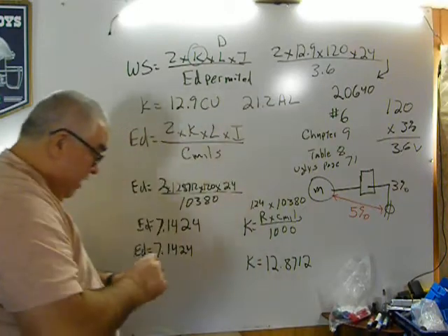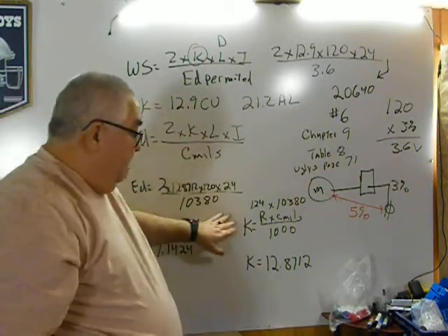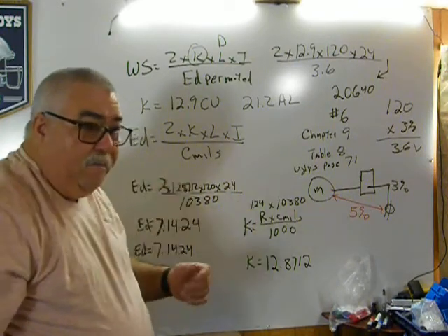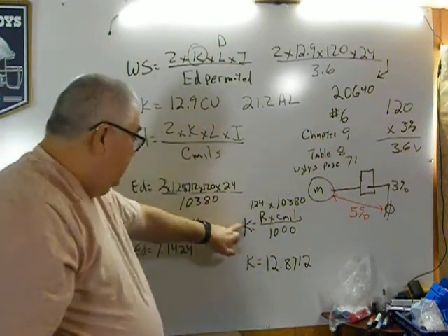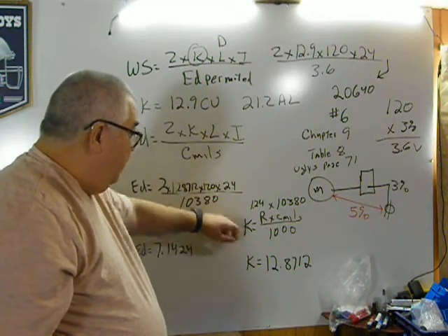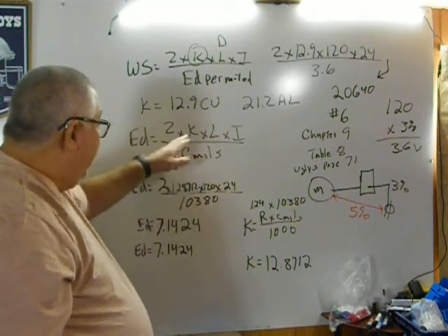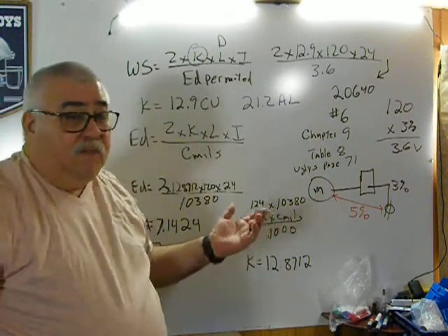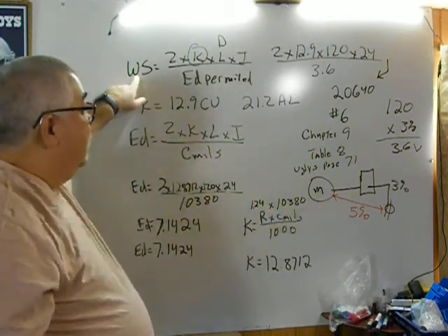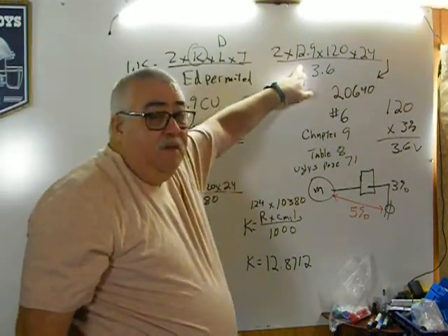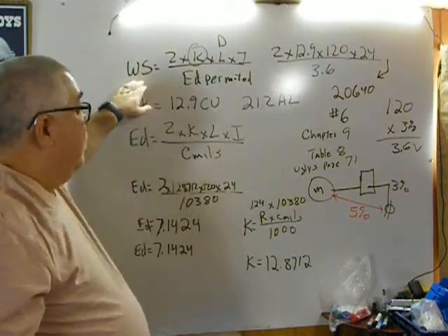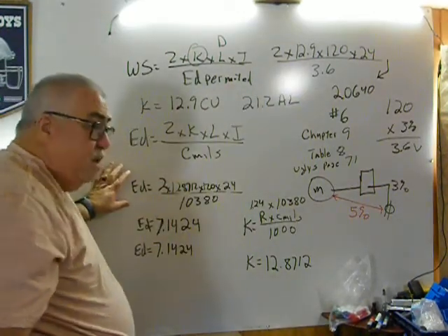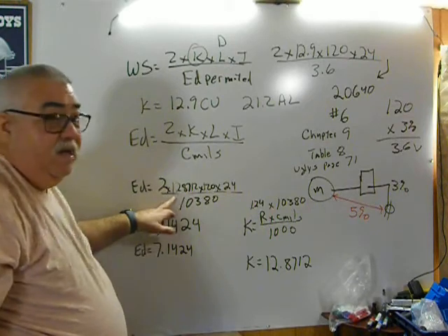In the PDF file that I uploaded with voltage drop formulas, this is on there. So all you have to do is find the exact K. Here we can use an approximate because we don't know our wire size. We're trying to find a wire size, so we can use an approximate number. If we're trying to find voltage drop in the system, then we need the exact number.